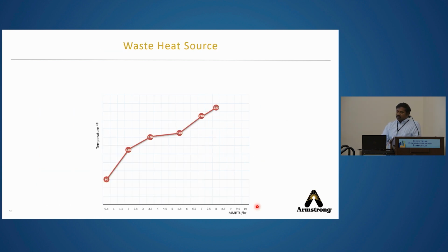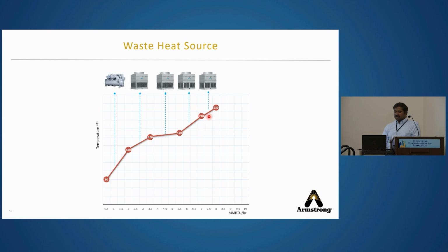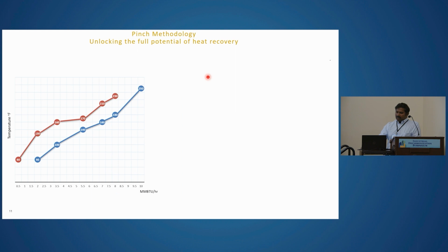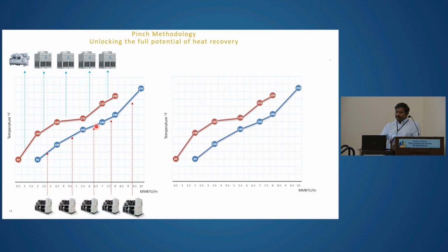The next study we need is: what is the waste heat available in the facility? When I say waste heat, it's nothing but the cooling which is required in a process. A specific process needs to be cooled from 230 to 210, or another process needs to be cooled down from 210 to 170. And all this heat, or the cooling done on the process, or the waste heat from the process, is vented to the atmosphere with the help of a cooling tower or a chiller. Now, after doing this analysis on the heat source side and sink side, we can plot that in a curve and identify what the pinch point is.